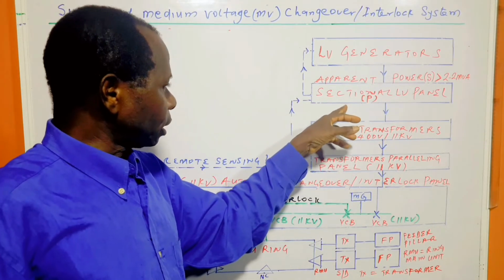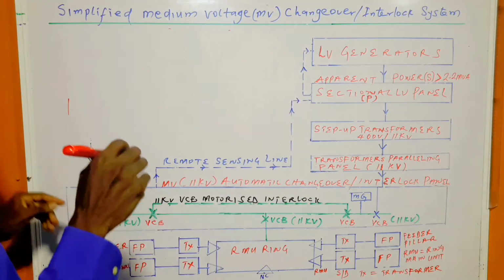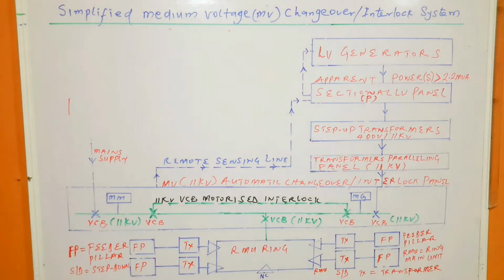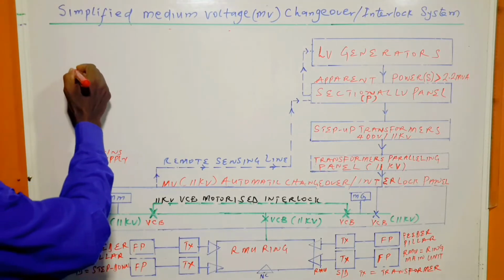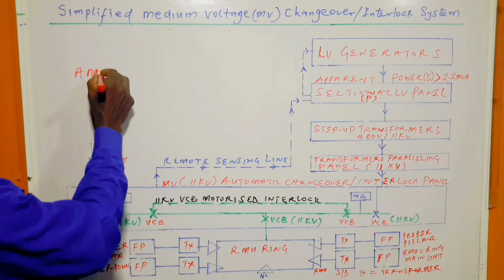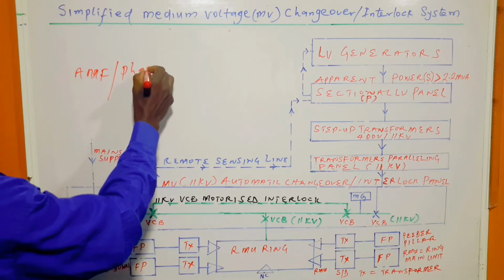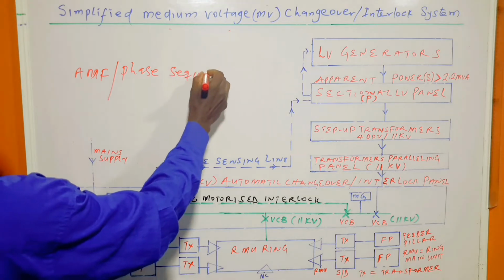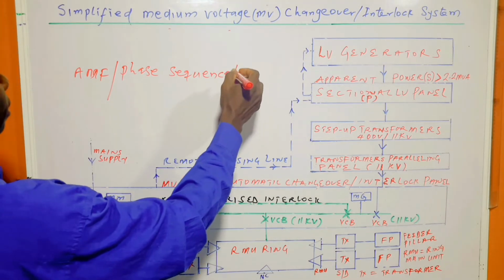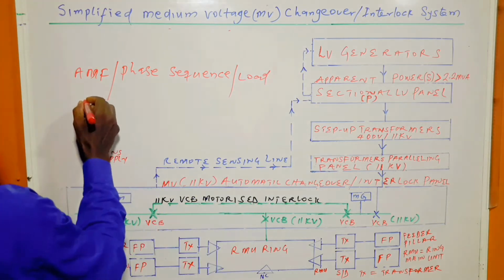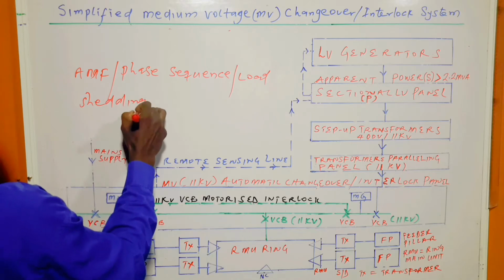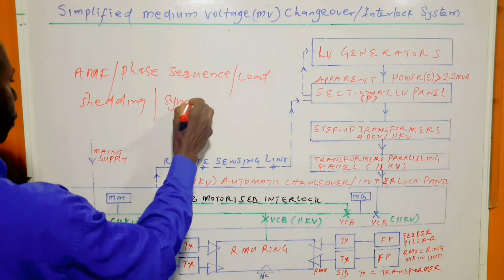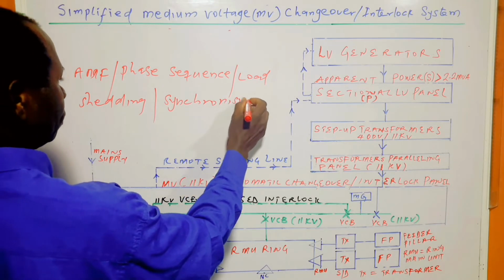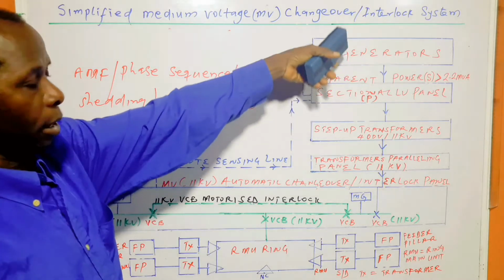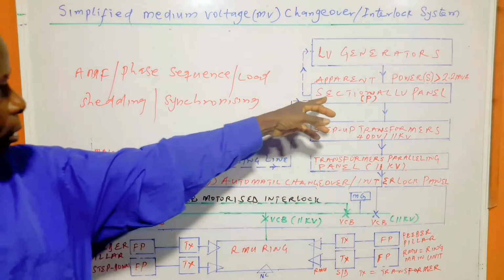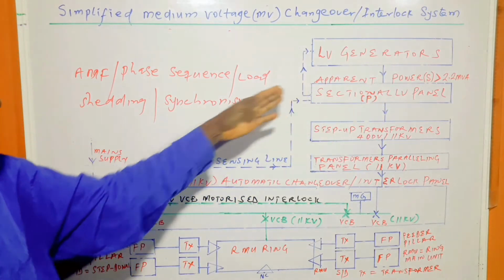Now this same panel P is a multipurpose panel, and it performs the functions of automatic mains failure device, AMF, phase sequence, load shedding, and synchronizing the generators. That is what this sectional LV panel does.